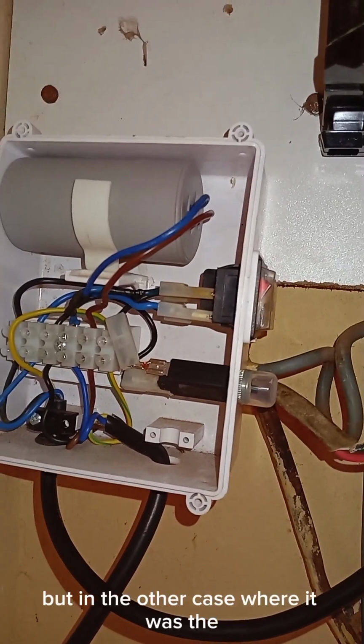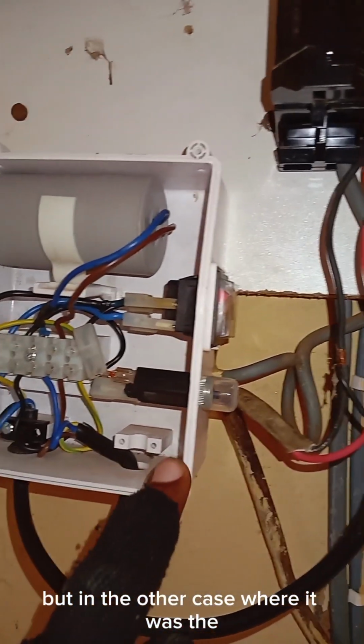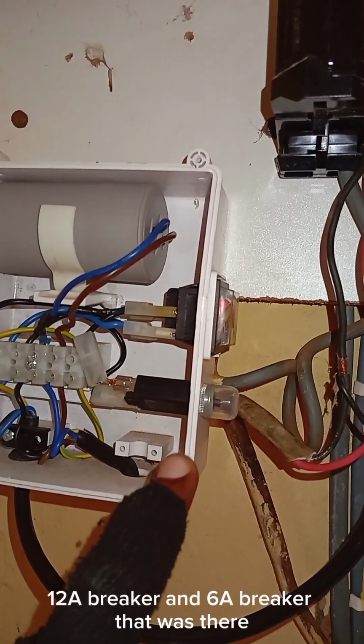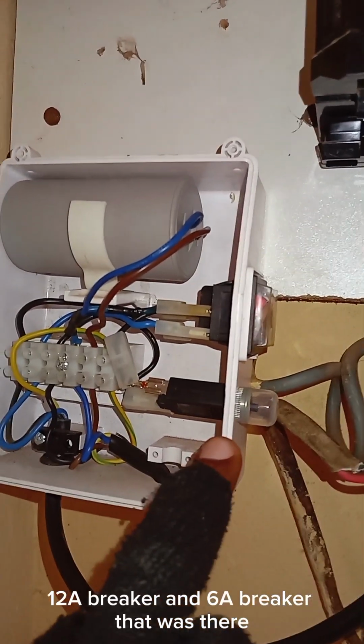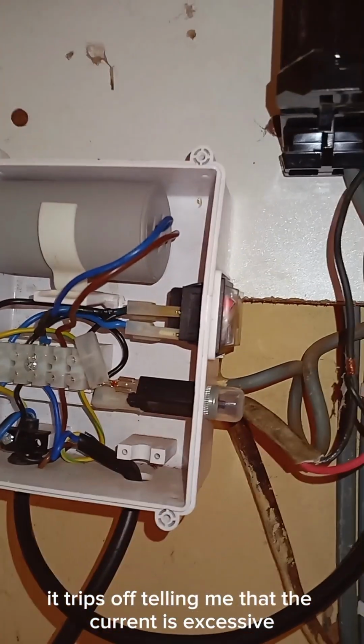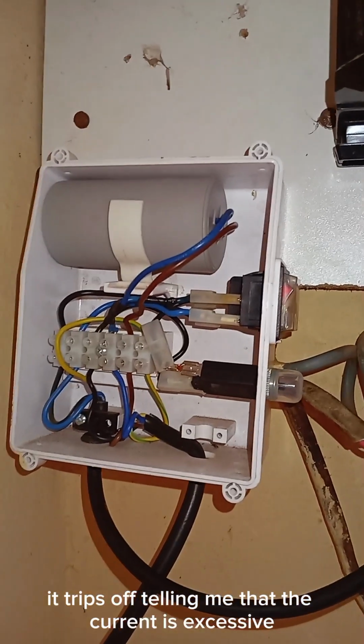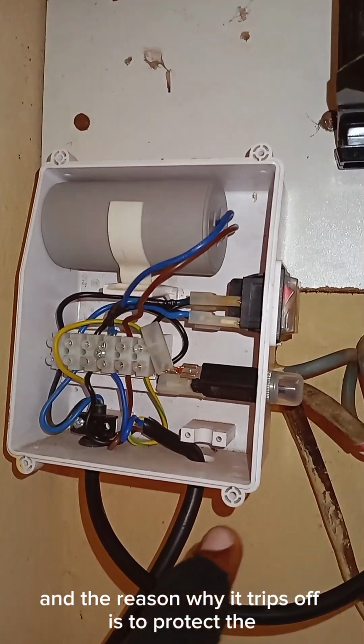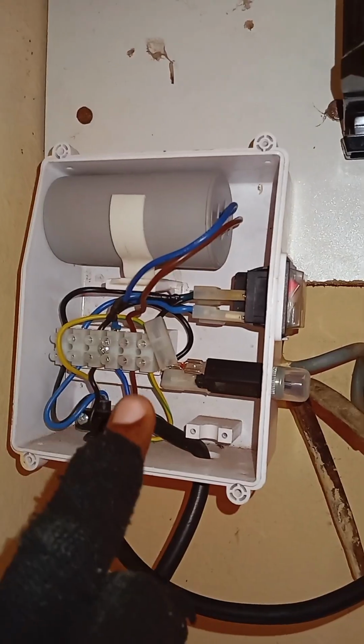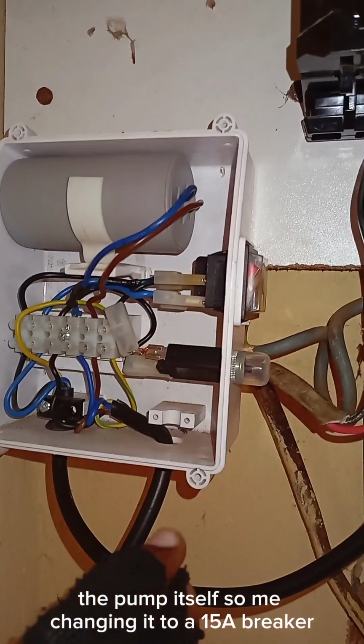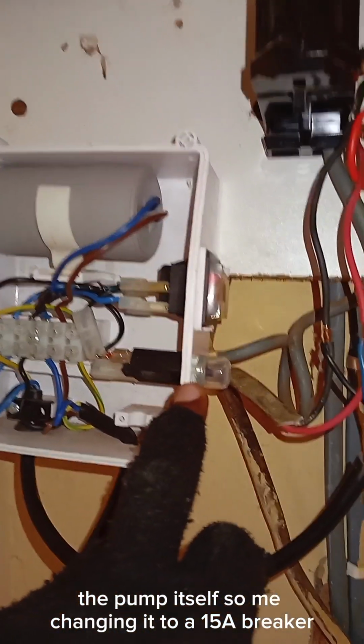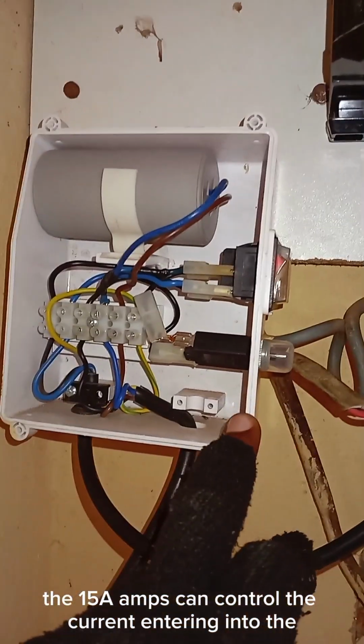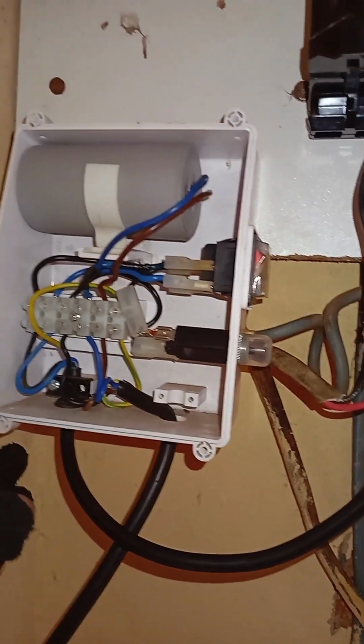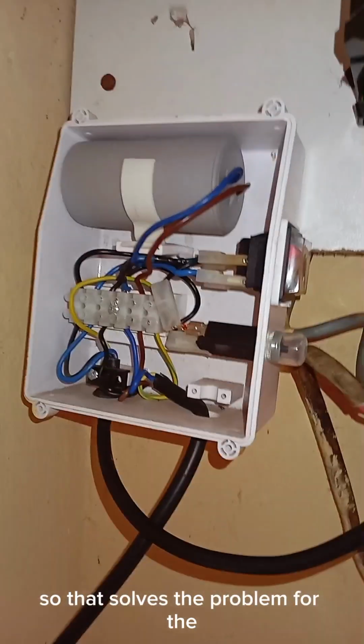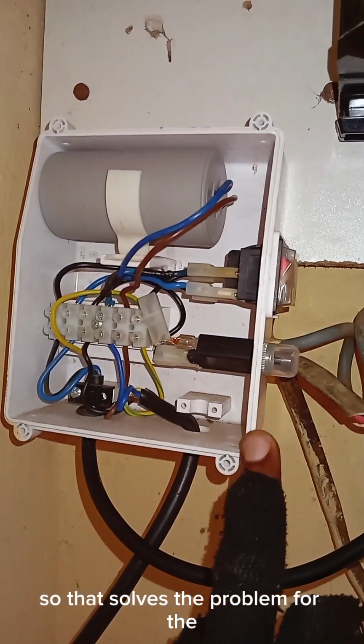But in the other case, where it was the 12 amps breaker and the 6 amps breaker that was there, it tripped off, telling me that the current is excessive, and the reason why it trips off is to protect the pump itself. So by changing it to a 15 amps breaker, it means that the 15 amps breaker can control the current entering into the control box and entering into the pump.